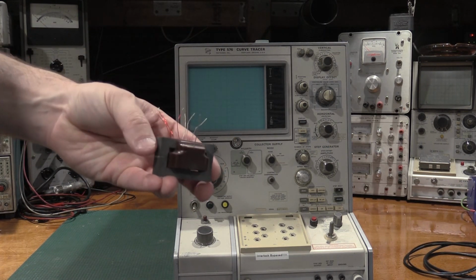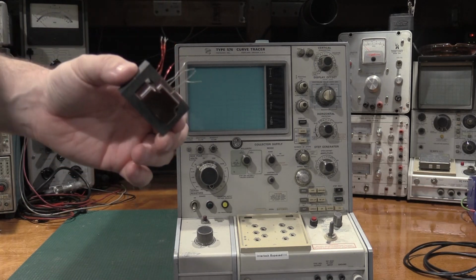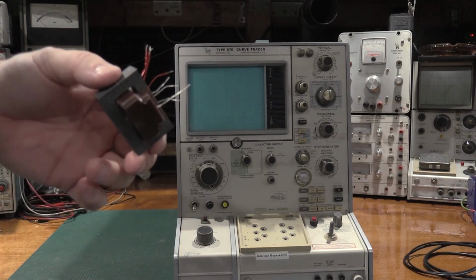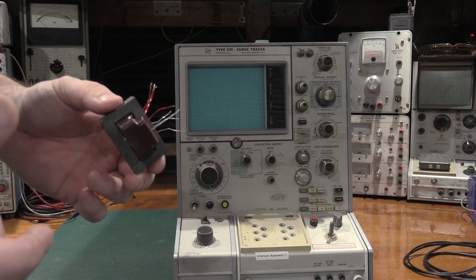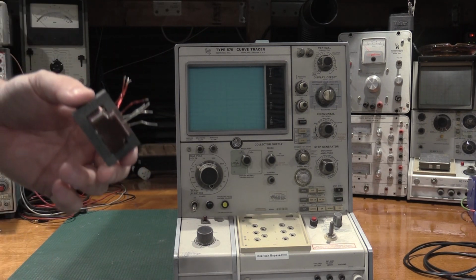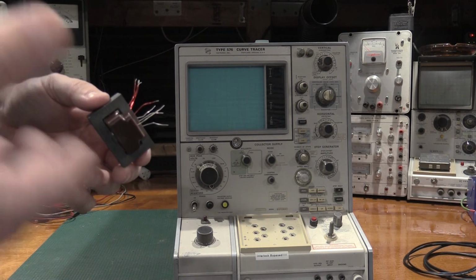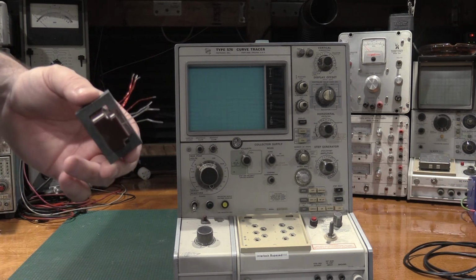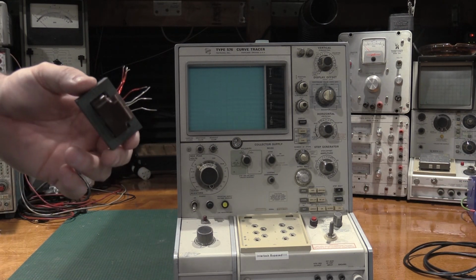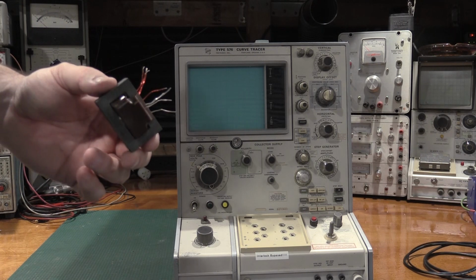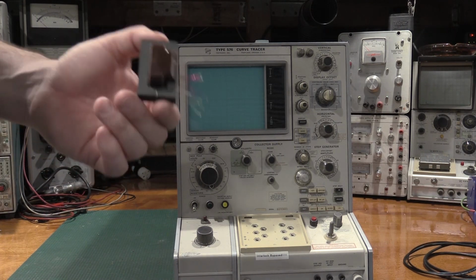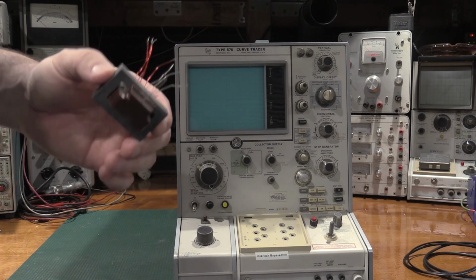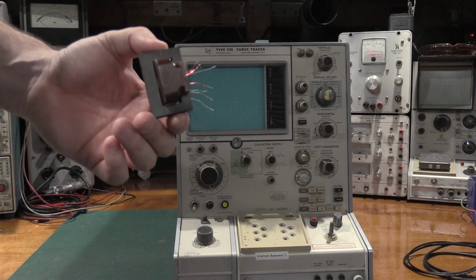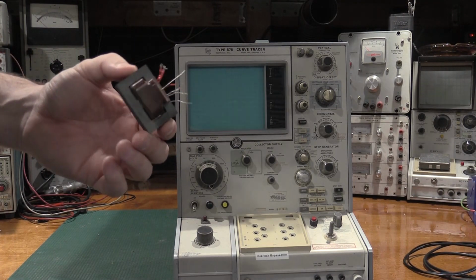All of these are bad at this point. They have a leakage current that's coming out of the epoxy, and the behavior that mine exhibited was it would run for about half an hour, and then it would act like it was power cycling. It wasn't really power cycling. What was happening is the 75-volt reference rail was collapsing due to the overcurrent being tripped because of the power transformer. The transformer was cooling off, overcurrent was hitting, and then it was coming back.